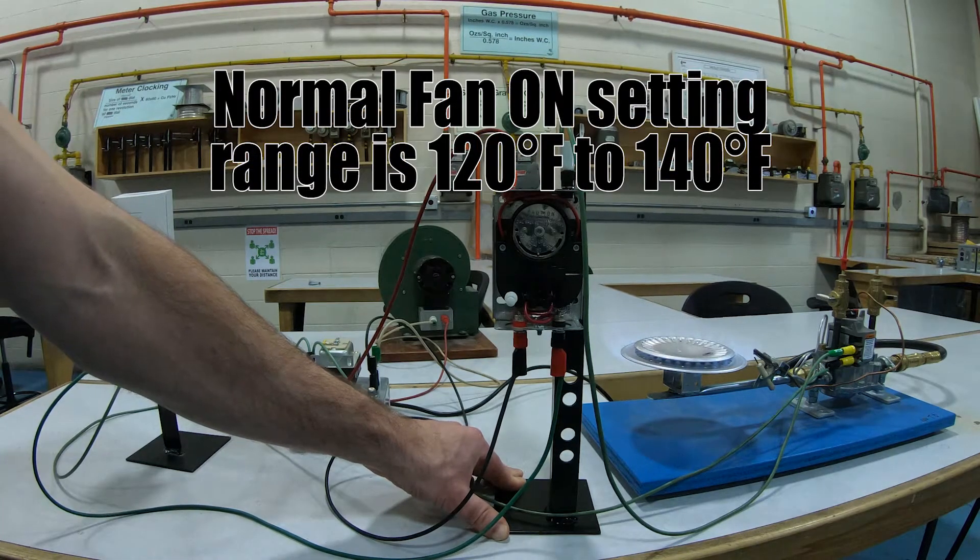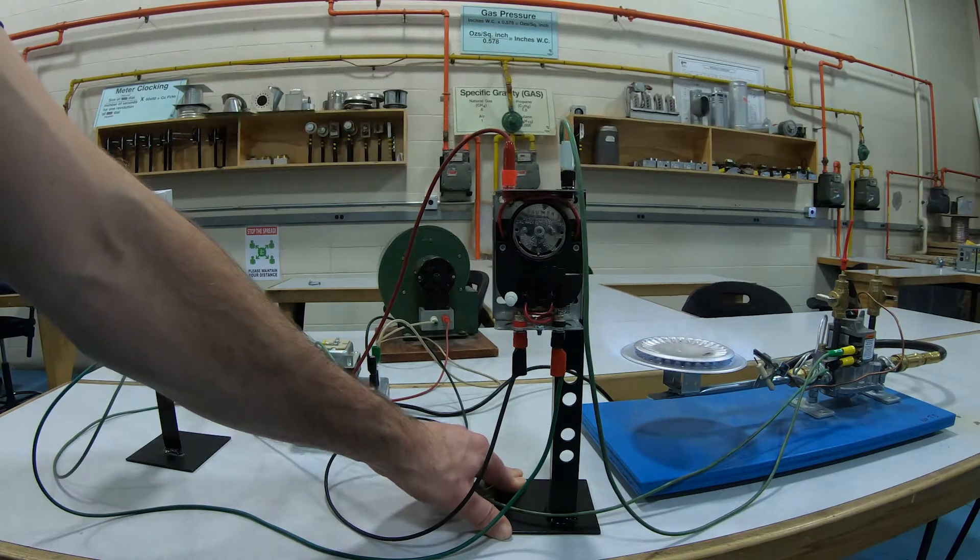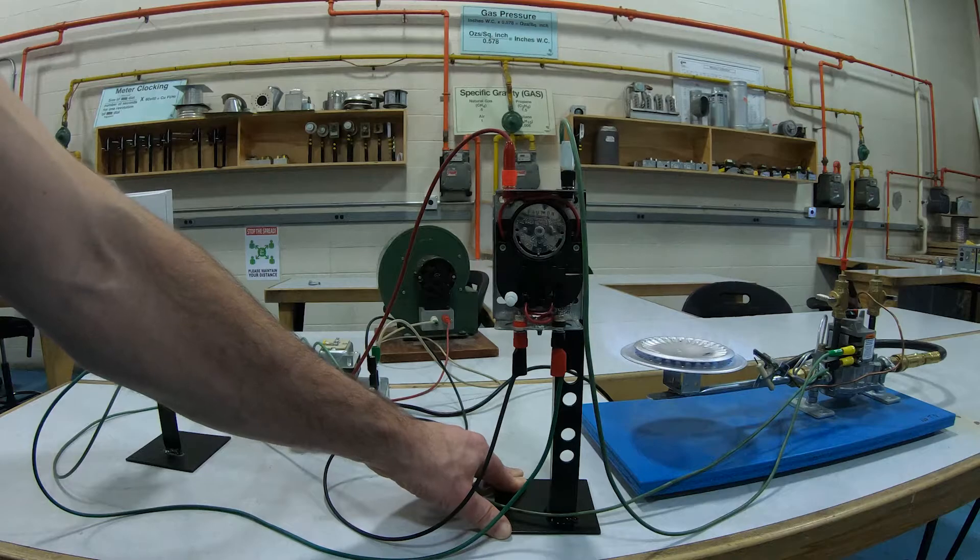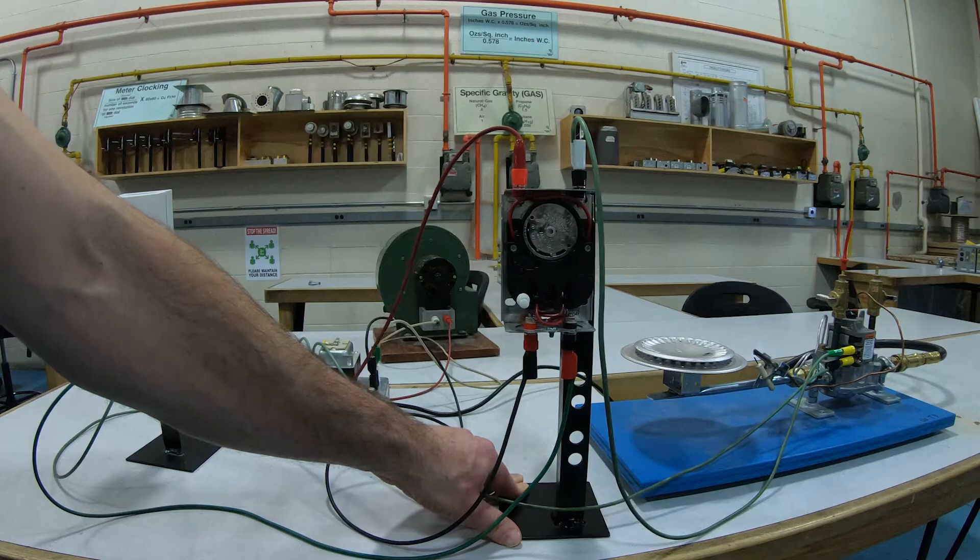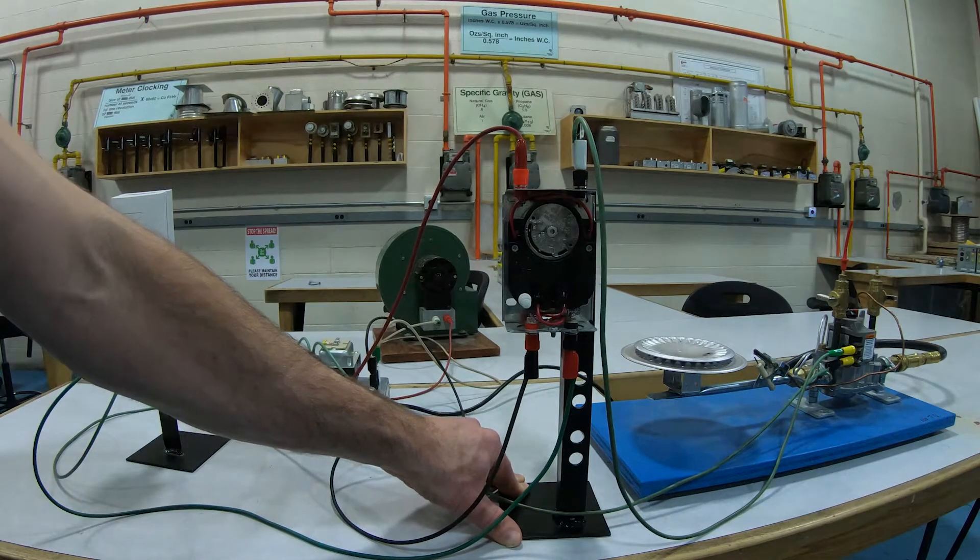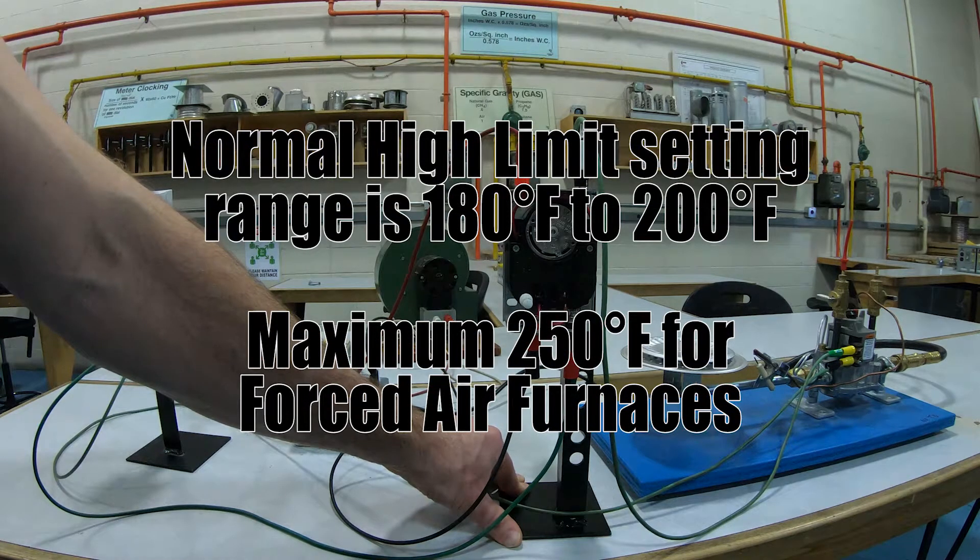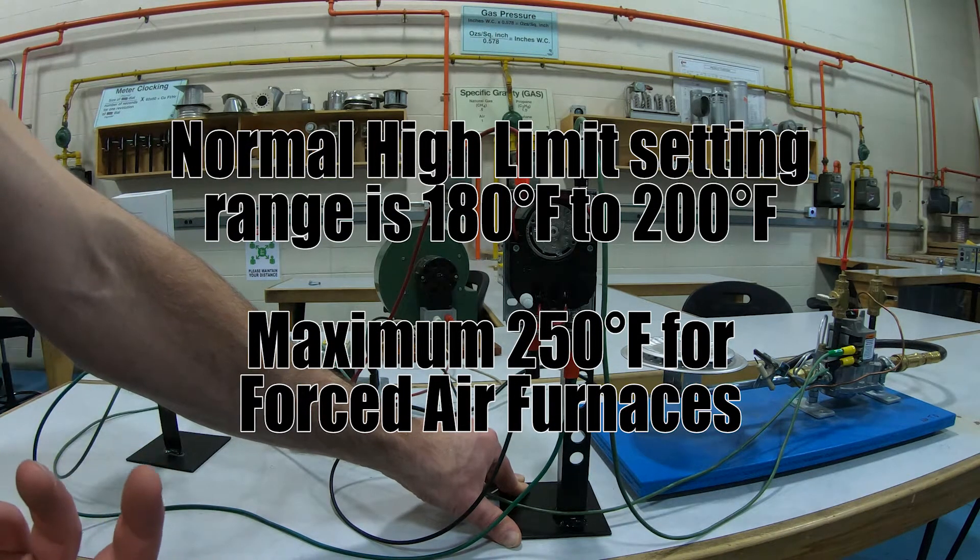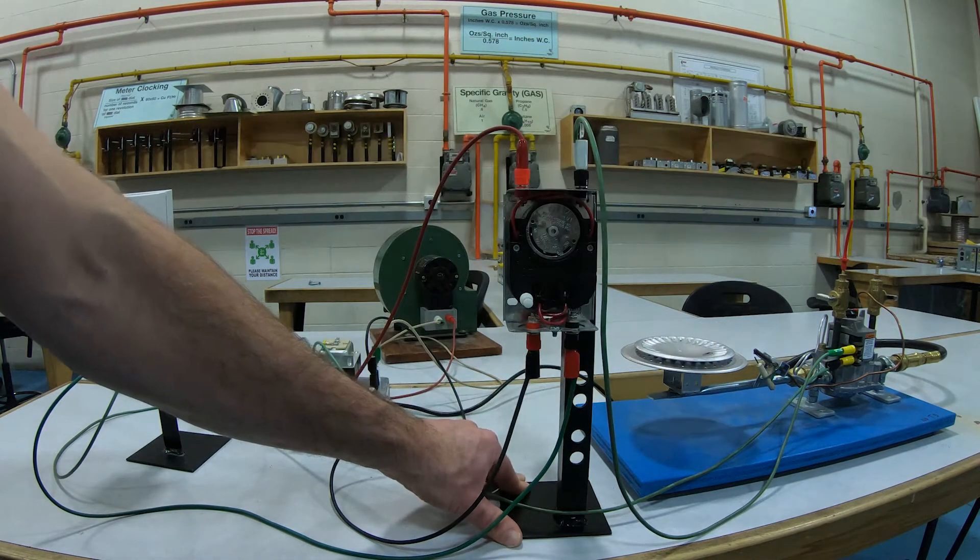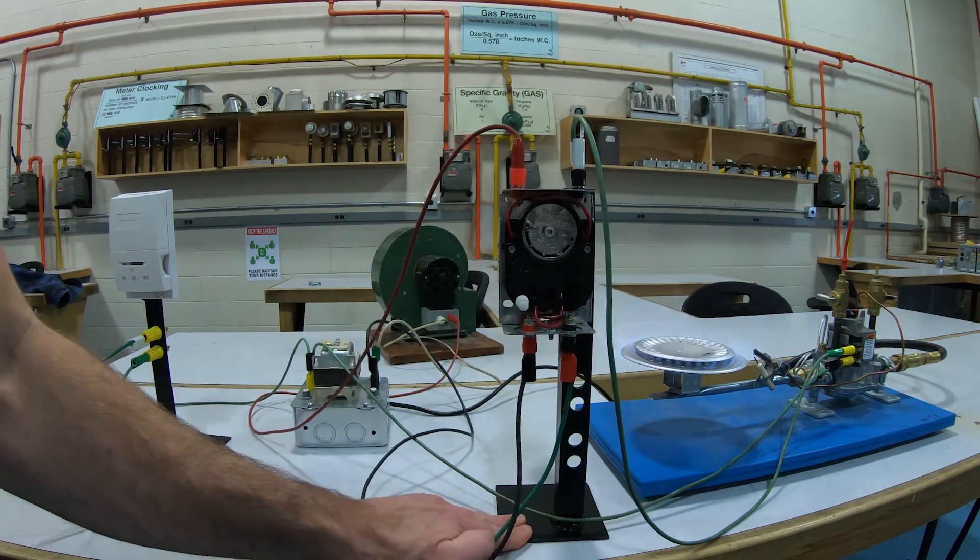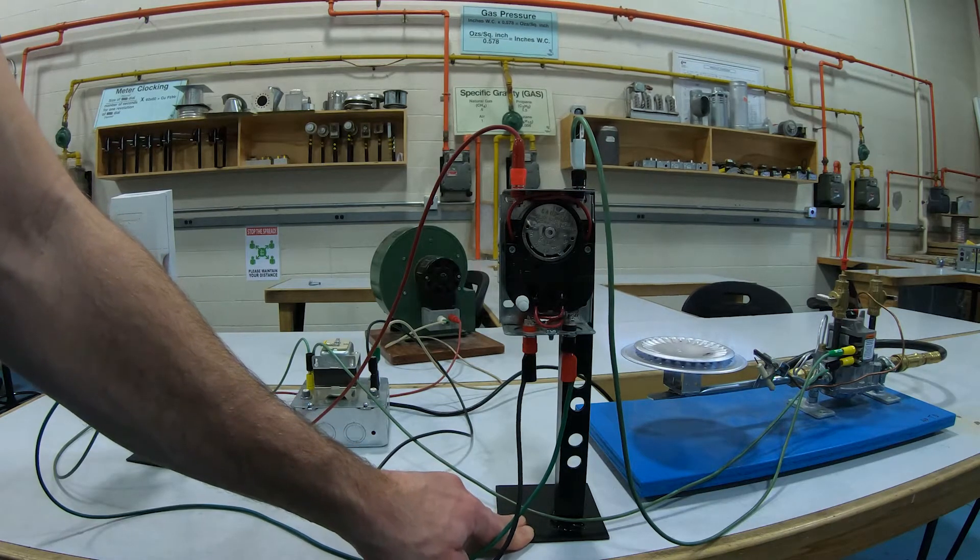Now we're going to simulate a problem. We're going to go into high limit very quickly. Apparently we went into high limit really fast because it was directly exposed to flame. Our high limit setting is at 200 degrees Fahrenheit, but that generally ranges between 200 and 180 degrees Fahrenheit. As you can see there though, we cooled down and the burner came back on.